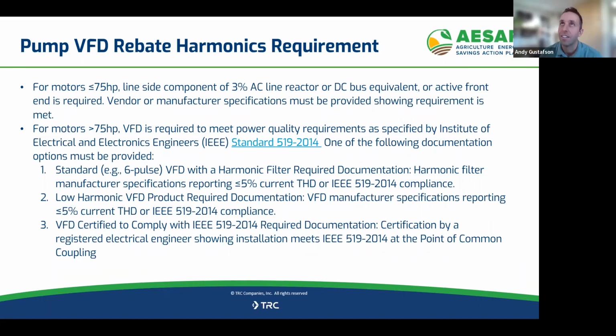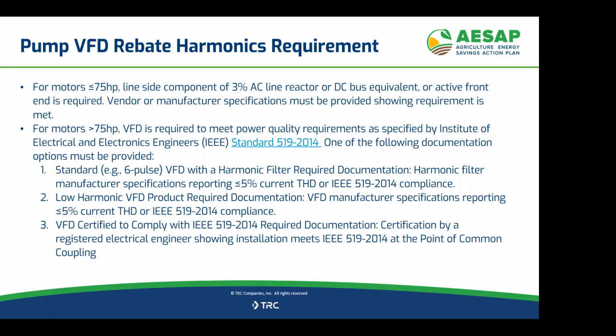So when you're talking about a filter, what specifically is that filter? Are we looking at capacitors? Something to reduce heat? It's to reduce total harmonic distortion. So it's called a harmonic filter specifically.